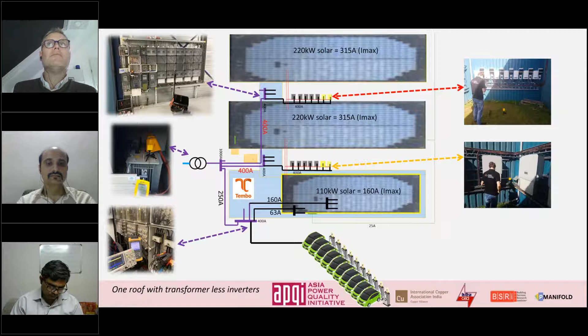At this cabinet I could not find a thing, but at this cabinet, I found the same, but the phase was in the opposite direction. So that means these inverters are talking to these chargers. The current jumps up and down at 16 amps, and 16 amps at 550 hertz is really terrible in your cables, and it will destroy a lot.